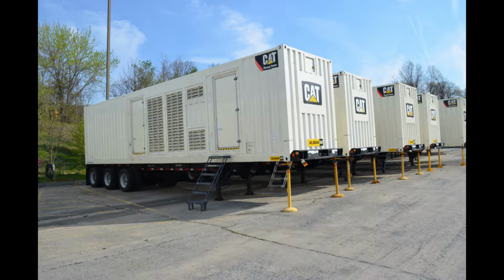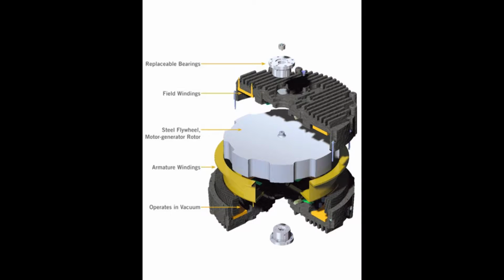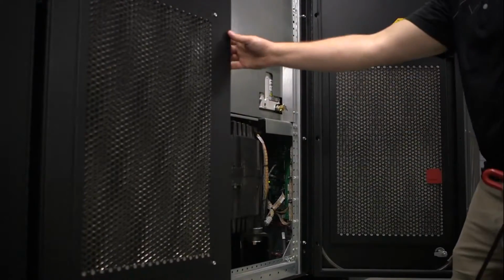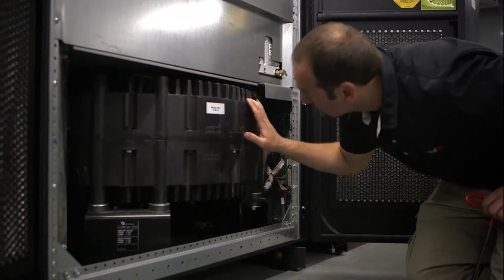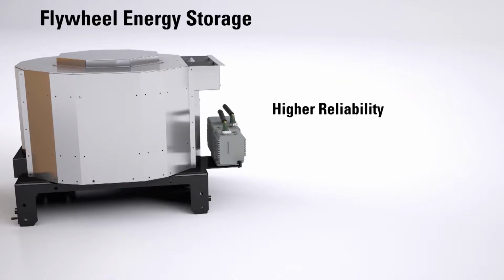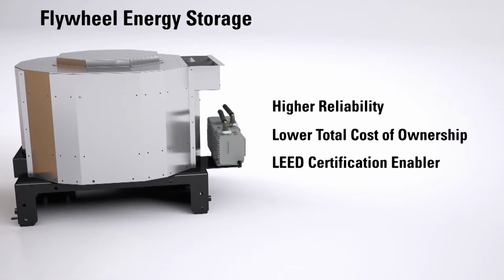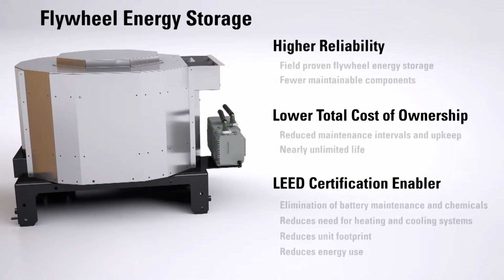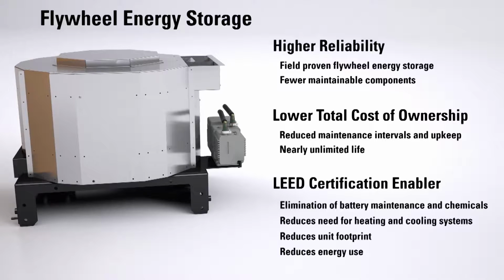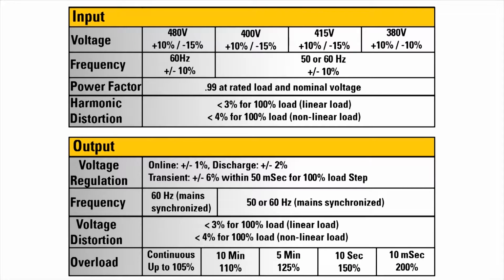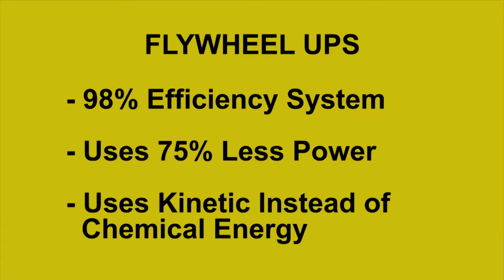Let's talk about the Alban CAT flywheel system that we have in our rental fleet. The flywheel system uses the inertia of a high-mass spinning flywheel to provide short-term ride-through during the event of a power loss. The flywheel also acts as a buffer against power spikes and sags, since such short-term power events are not able to appreciably affect the rotational speed of the high-mass flywheel. A UPS flywheel system requires no batteries. The UPS and flywheel are in one compact system and use about a quarter of the space that its battery counterpart of similar size. The UPS flywheel system stores kinetic energy as opposed to chemical energy.